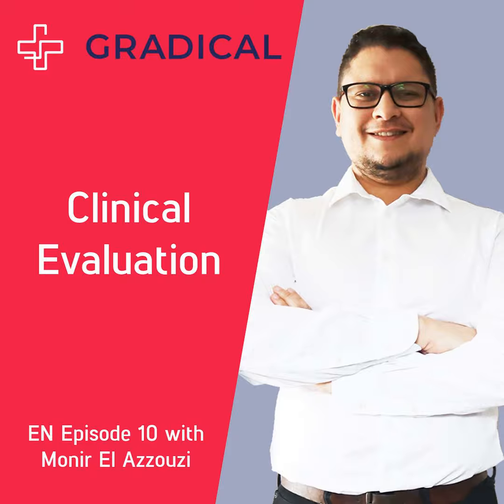So mainly first, if your device is a class 3 device, so this is also important. If it's a class 3 device, mainly you'll have to go through a clinical investigation. There is no real choice, unless you have really good justification, which is this equivalence, this extension can be one of the exceptions, but mainly they will ask you to have really some clinical investigation.